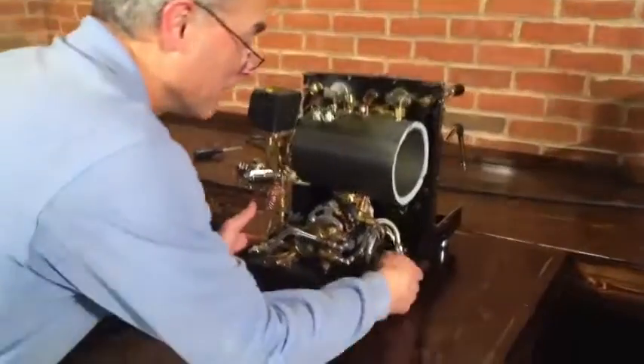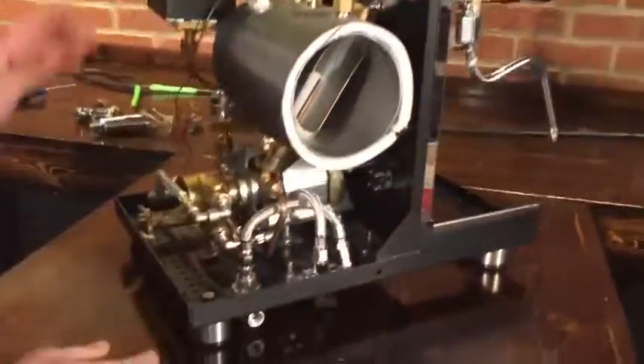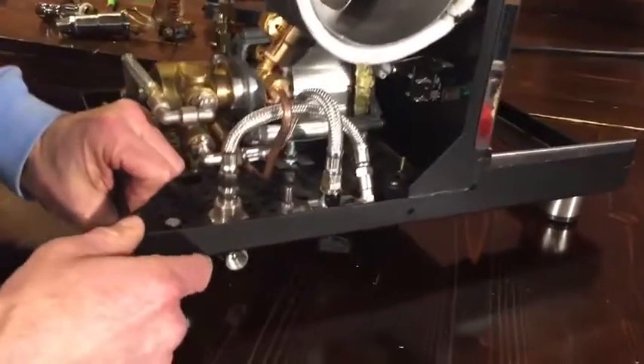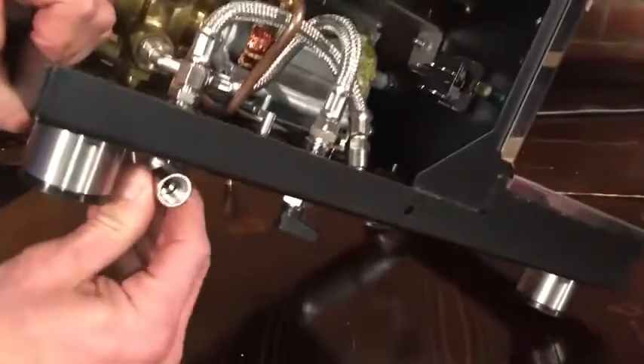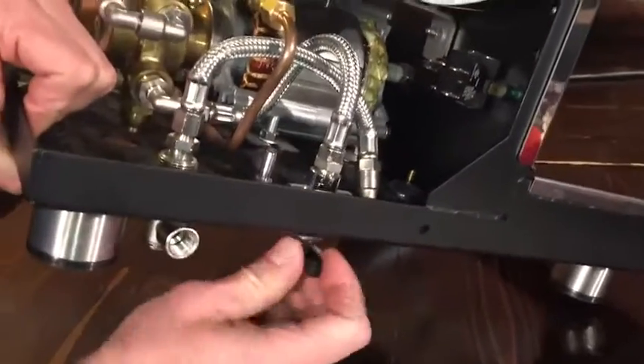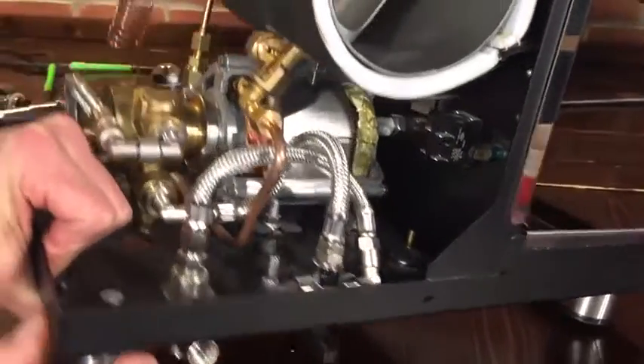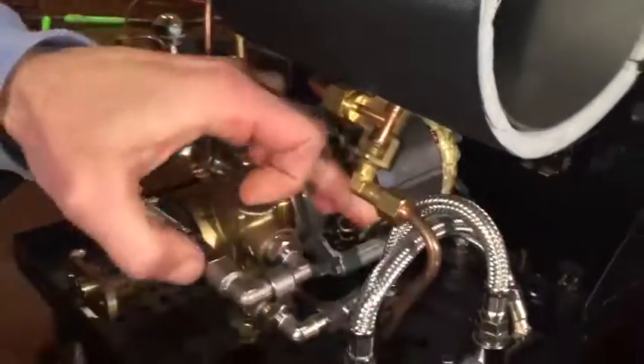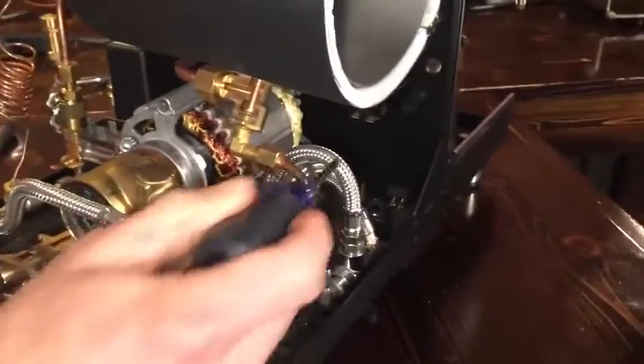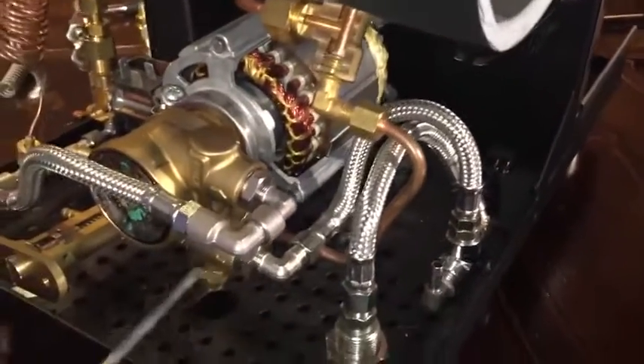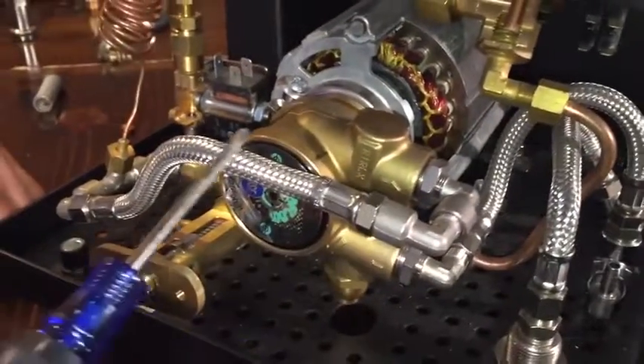So we're going to follow water flow through the machine. The water comes either in through the water line connection or through where the reservoir connects. You have a valve here that controls which one you're drawing from. Water flows through this braided stainless steel tube here, into the pump, and out of the pump.